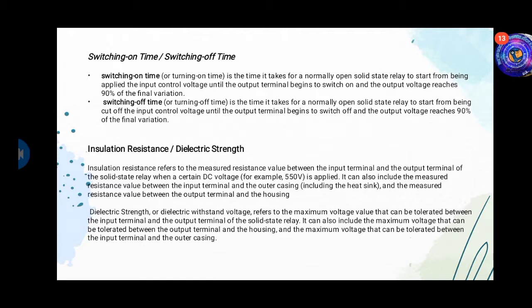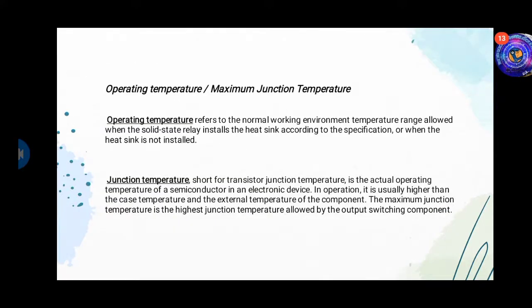Dielectric strength, or dielectric withstand voltage, refers to the maximum voltage value that can be tolerated between the input terminals and the output terminals of the solid-state relay. It can also include the maximum voltage that can be tolerated between the output terminals and the housing, and between the input terminal and the outer chassis. Operating temperature and maximum junction temperature: operating temperature refers to the normal working environment temperature range allowed when the solid-state relay is installed with the heatsink according to the specification, or when the heatsink is not installed.